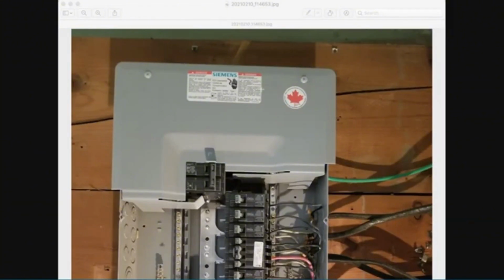Here's our conduit, and inside it, coming from the hydro meter, here is the neutral wire. It's going to come in. I can either connect it to this neutral bus bar or bring it to this one. Because the wire is coming in all the way over here, I'm going to work as cleanly as possible, so I ran the neutral to the neutral bus bar over here.